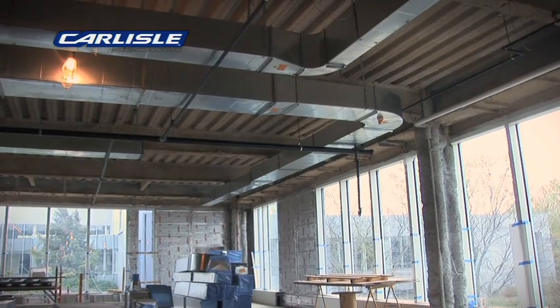We've always sealed ducts in our shop, one form or another, and over the years we've experimented with a number of products. We used to use a caulk-on. We would make the duct and then caulk the longitudinal seam and then use a brush to smooth it out. It is a painstaking process, and to make matters worse, if you deliver it before it dries, it'll crack on the truck on the way to the job site, making your test much more likely to fail.